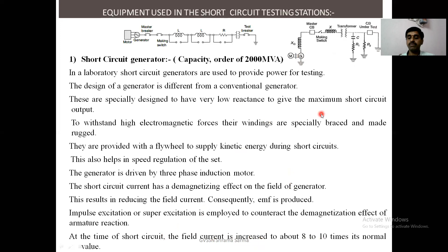The short circuit current generally has a demagnetizing effect on the field of the generator. Because of the demagnetizing effect, what happens? It reduces the field current. Therefore, the EMF will be reduced. So, for this case, an impulse excitation or super excitation is employed to counteract the demagnetization effect of the armature reaction. So at the time of short circuit, field current is increased to about 8 to 10 times its normal value. So these are the special design features that make the short circuit generator different from a conventional generator. That means low reactance and impulse excitation.